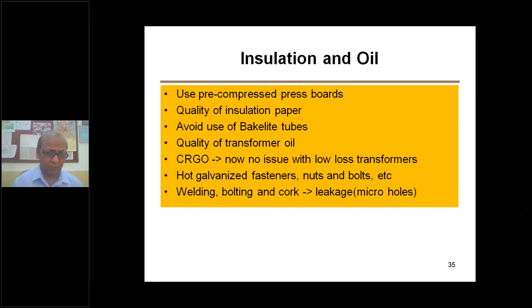Then I come to the design aspect, what the designer should take care of. No doubt all the technical people do good design, but they are also under pressure from the management to economize the design. Still, by making certain compromises, the life of the transformer should not be compromised. So proper clearances and ducts for cooling are important so that hot spots do not appear, otherwise there will be failures, and we will have too many failures in the warranty period. Recommend use of a corrugated cylinder between HV and LV for better cooling.